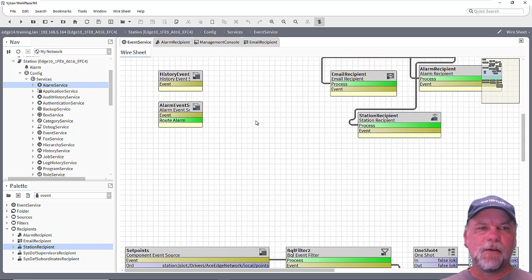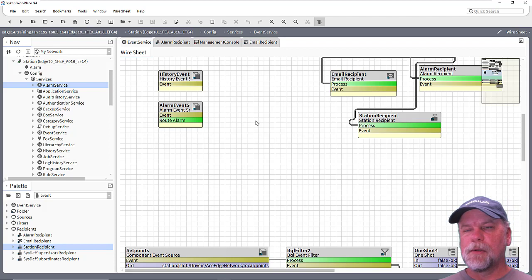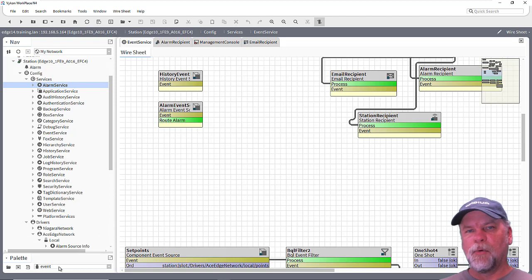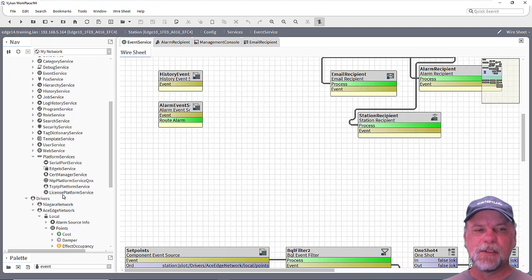Okay. Now, another thing where this might be useful is this edge controller in particular. With the edge controllers, there's no onboard battery backup like maybe a legacy JACE 6, 3, or 2 had. There's no critical data service. So when you look under the platform services, there's no data recovery service here. The edge controller doesn't have onboard SRAM or anything of that nature.